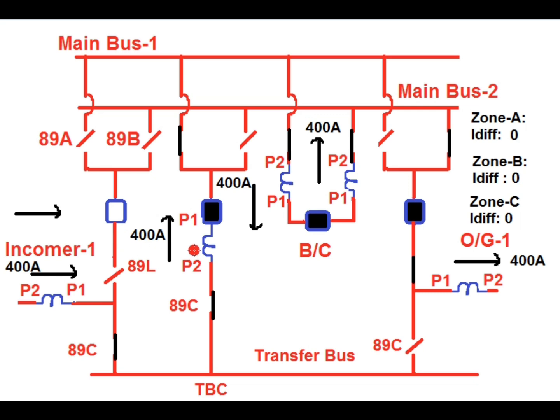Apart from zone A and zone B, there is another zone — zone C. Zone C will be activated if 89C of the TBC is closed. In this case, since incomer 1 is diverted to the TBC bay, zone C — which is the protection zone for the TBC bay — will be activated. This zone includes the TBC CT and any of the incoming or outgoing feeders connected through it.